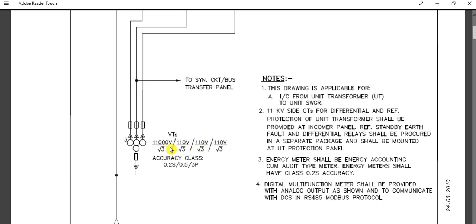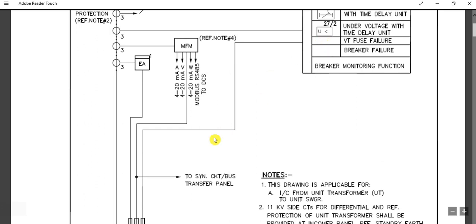This is an 11kV / 110V VT. The primary side is 11kV, since this is an 11kV feeder, and the secondary side outputs are 110/√3 volts. The VT has three accuracy classes: 0.2S, 0.5, and 3P. The 0.2S accuracy class winding is for the energy audit meter, the 0.5 accuracy class is for normal metering purposes, and the 3P accuracy class winding is connected to the numerical protection relay.